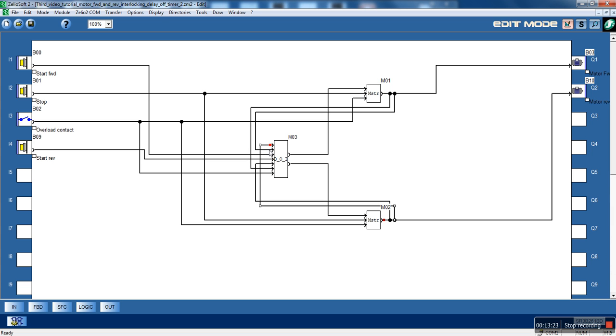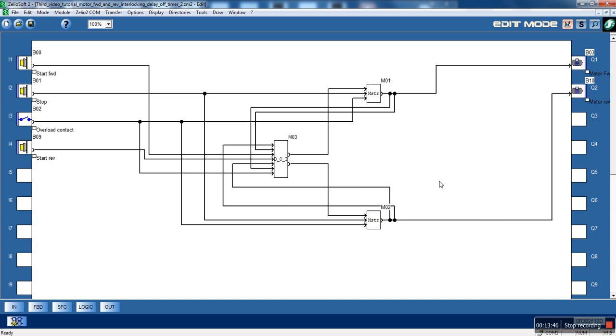These four inputs — or rather two inputs — this input and this input are common; they are the same point, but in the macro we have to have every input mapped separately no matter where it's from. They must have a different input in the macro. That's why we have two times the same input — it's because of the Zelio software, no other reason. That's what we have to be careful about.